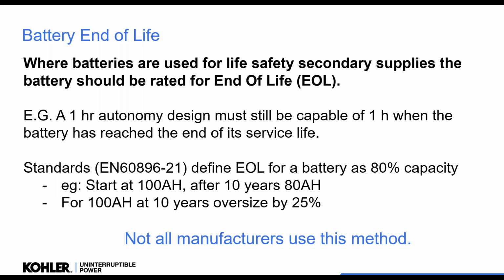So another thing that isn't specified in a lot of places is that a battery will age. Okay, so if it's a 10-year battery, it's designed to lose 20% over its lifespan of 10 years. So if we started with an hour, we're not going to have 1 hour at the end of life. Okay, so if we still want the autonomy, which we should have at the end of life, the battery has to be oversized by 25% at day one, so that when it gets to the end of life, it's lost 20% and we're at the required autonomy. Okay, it's not written in many places. A lot of people don't consider it, but really this is life safety, and you should always have the autonomy that it's designed for. Okay, so that does mean end of life.